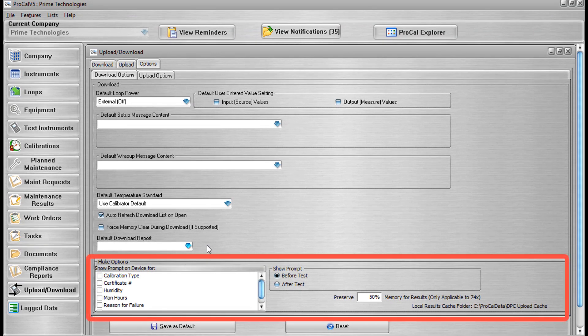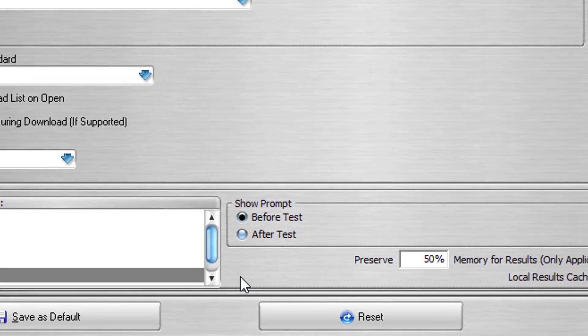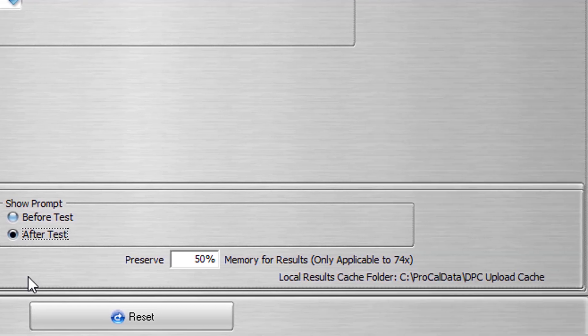In the Fluke Options section, the Show Prompt on Device For section provides additional information about the tests performed in the field through six checkboxes. If a checkbox is selected, the tester will be prompted for that information, and their responses are saved as part of the testing information on a per tag ID basis. The tester can decide if the prompts will be presented before or after the test using the Show Prompt Before or Show Prompt After radio button. Every calibrator has a certain amount of memory broken up into tasks and results. By downloading, we erase the results memory and replace the tasks memory with newly created procedures. The Preserve 50% Memory for Results section allows the tester to save a defined percentage of the memory for the calibration results.